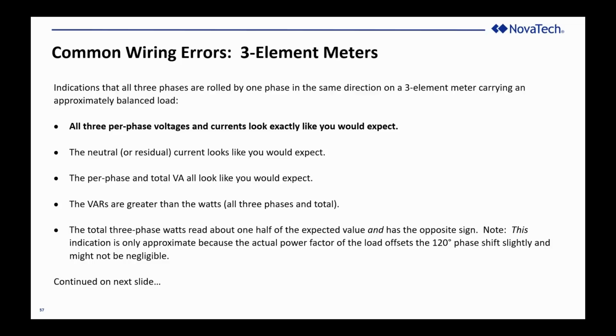So if all three phases are rolled in the same direction, A is on B, B is on C, and C is on A. Neutral is on neutral. I'm not going to deal with wiring errors where the neutral is on A and the B and the C are on neutral. That's less common. It can be ruled out with a Fluke. If your neutral is hot, you've got a problem.